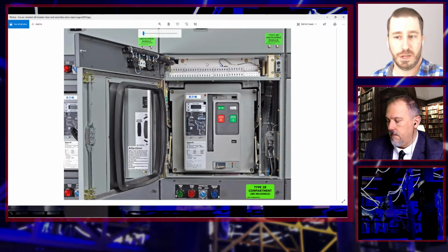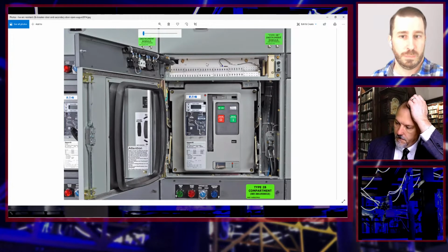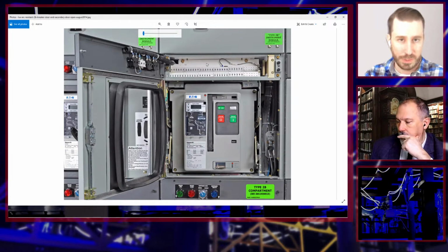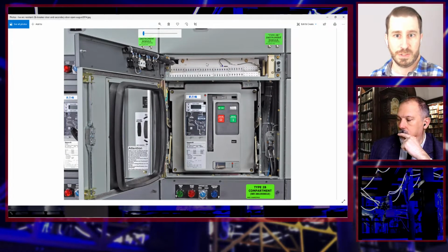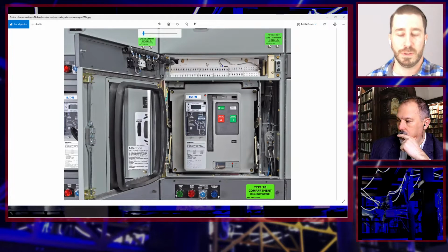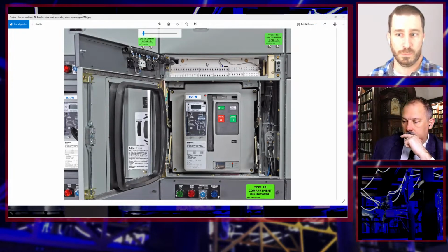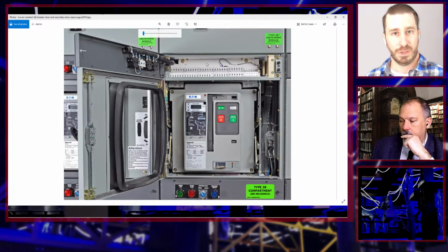Commonly, from an equipment side, where you'll start to see those suffixes for Type 2B are going to be in things like low voltage switchgear, as you've got shown, or medium voltage switchgear, or other things that are designed in such a way that the traditional equipment allows for compartmentalization from breakers and other control compartments. So, for instance, in motor control centers, you'll see manufacturers stop at a Type 2 because there's really not a compartmentalization between power and control components. They all kind of share the same space with that equipment design.